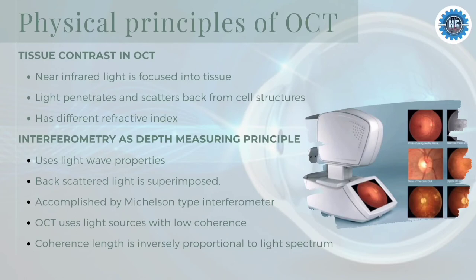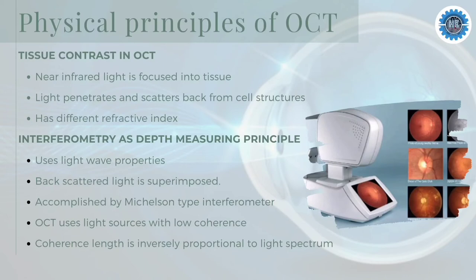The second principle is Interferometry as the depth-measuring principle of OCT. Optical Coherence Tomography utilizes the wave properties of light for depth measurement, namely the interference caused by superposition of the electrical field amplitude. The back-scattered light is superimposed with a reference beam, usually accomplished by an interferometer setup such as the Michelson-type interferometer. The superimposed beams show interference if the light of the two beams is coherent, which depends on a fixed phase difference of the waves in the two arms of the interferometer.